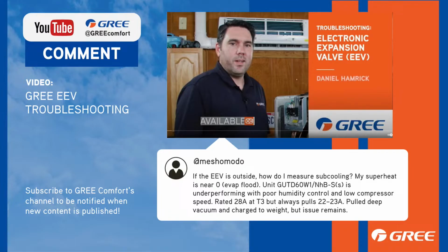Got a unit GUTD60W1NHBSS is underperforming with poor humidity control and low compressor speed. It's rated at 28 amps at T3, but always pulls 22 to 23 amps. Pulled a deep vacuum and charged to weight, but issue still remains.